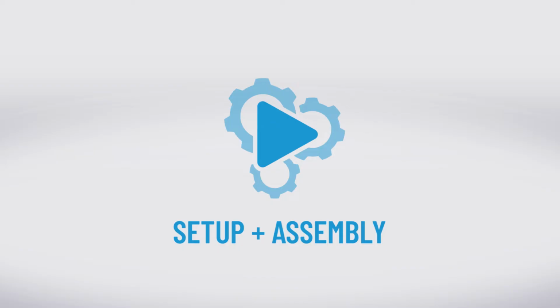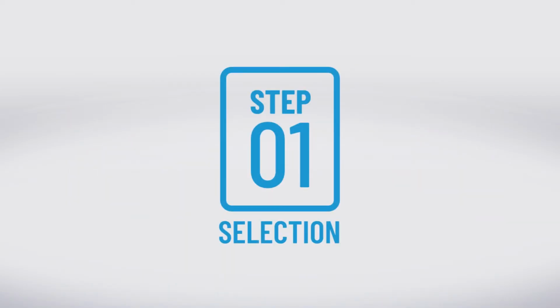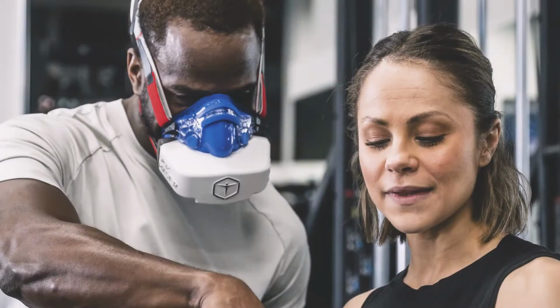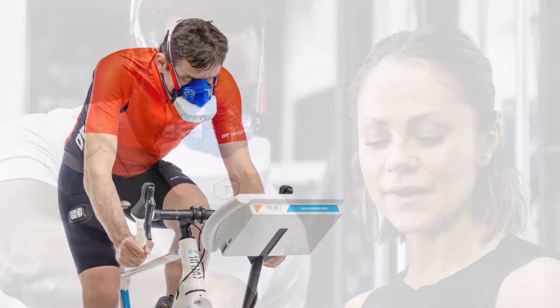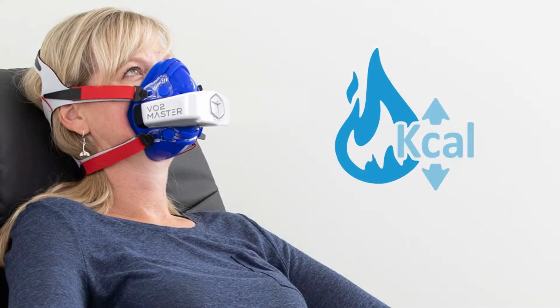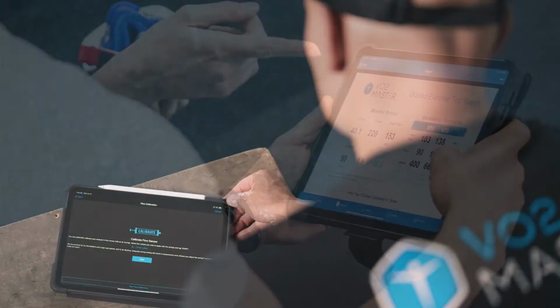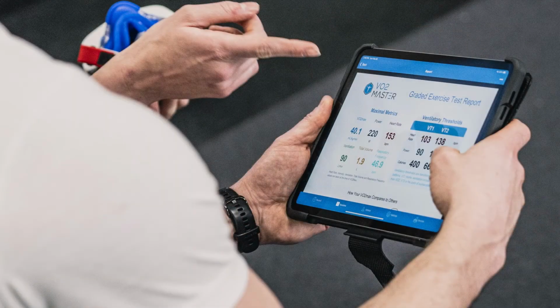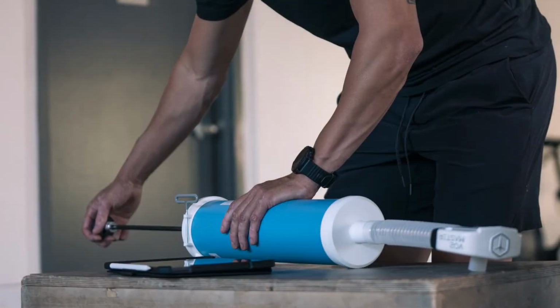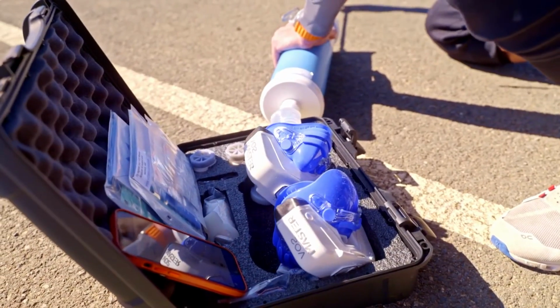Prior to performing any Vo2 Master assessment, we must complete a simple 3-step process. Step 1. We must select the type of test we are going to perform, either a performance or RMR test, as each test requires a different calibration process. For a performance test, we'll require the calibration syringe to be set to 3 liters, and the RMR test requires the syringe to be set to 1 liter. The remaining calibration procedures stay the same.